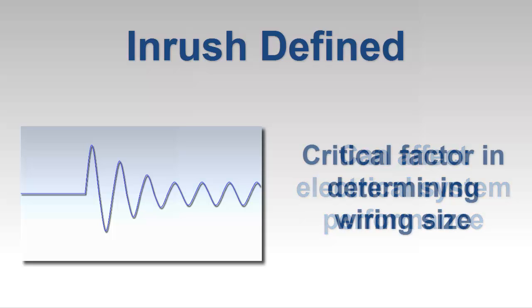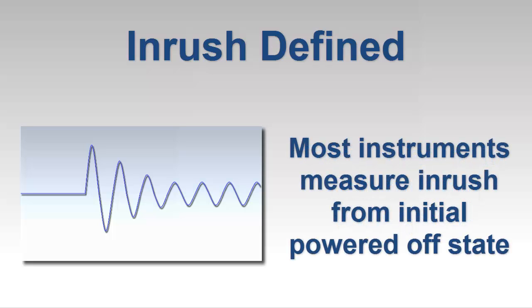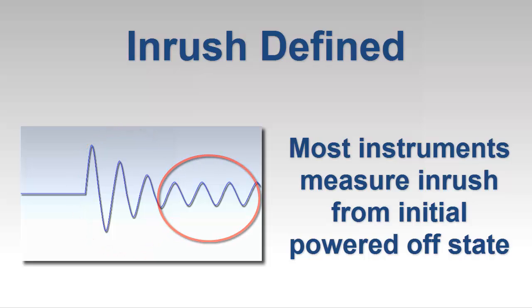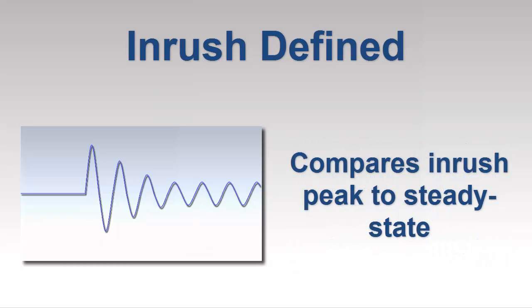Inrush is also a critical factor in determining the proper sizing of your network. Most instruments can only measure inrush in systems that are initially powered off. These instruments measure current and voltage starting with the initial powered down state, through power up, and finally steady state operation, which usually occurs within the first few seconds after startup. The instrument then compares the power up peak to steady state, and depending on the threshold criteria used, displays the inrush reading.